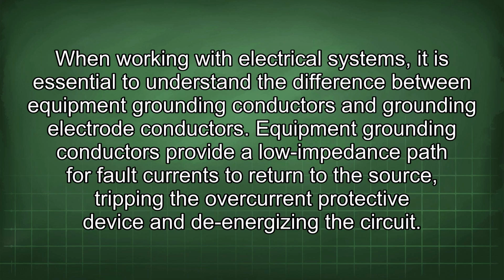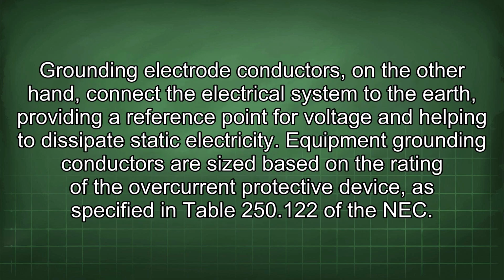When working with electrical systems, it is essential to understand the difference between equipment grounding conductors and grounding electrode conductors. Equipment grounding conductors provide a low impedance path for fault currents to return to the source, tripping the overcurrent protective device and de-energizing the circuit. Grounding electrode conductors, on the other hand, connect the electrical system to the earth, providing a reference point for voltage and helping to dissipate static electricity.